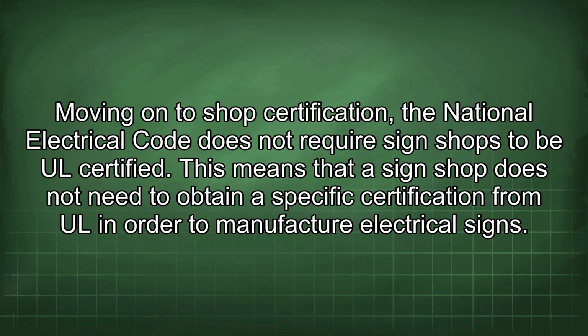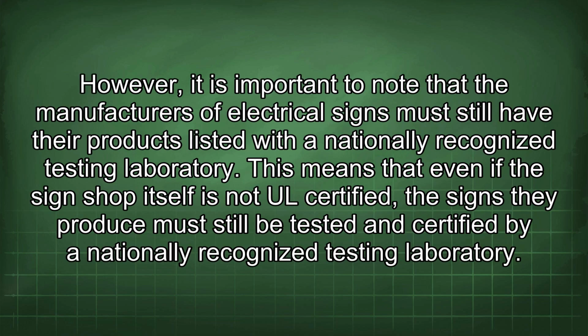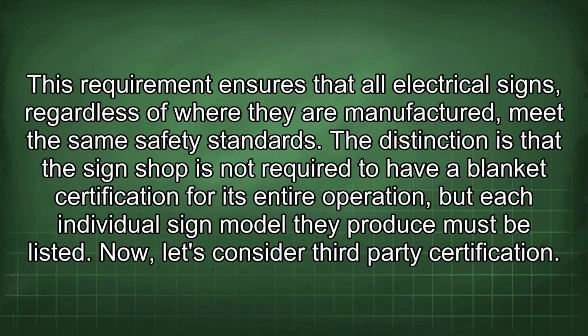Moving on to shop certification, the National Electrical Code does not require sign shops to be UL certified. This means that a sign shop does not need to obtain a specific certification from UL in order to manufacture electrical signs. However, it is important to note that the manufacturers of electrical signs must still have their products listed with a nationally recognized testing laboratory. This means that even if the sign shop itself is not UL certified, the signs they produce must still be tested and certified by a nationally recognized testing laboratory. This requirement ensures that all electrical signs, regardless of where they are manufactured, meet the same safety standards. The distinction is that the sign shop is not required to have a blanket certification for its entire operation, but each individual sign model they produce must be listed.